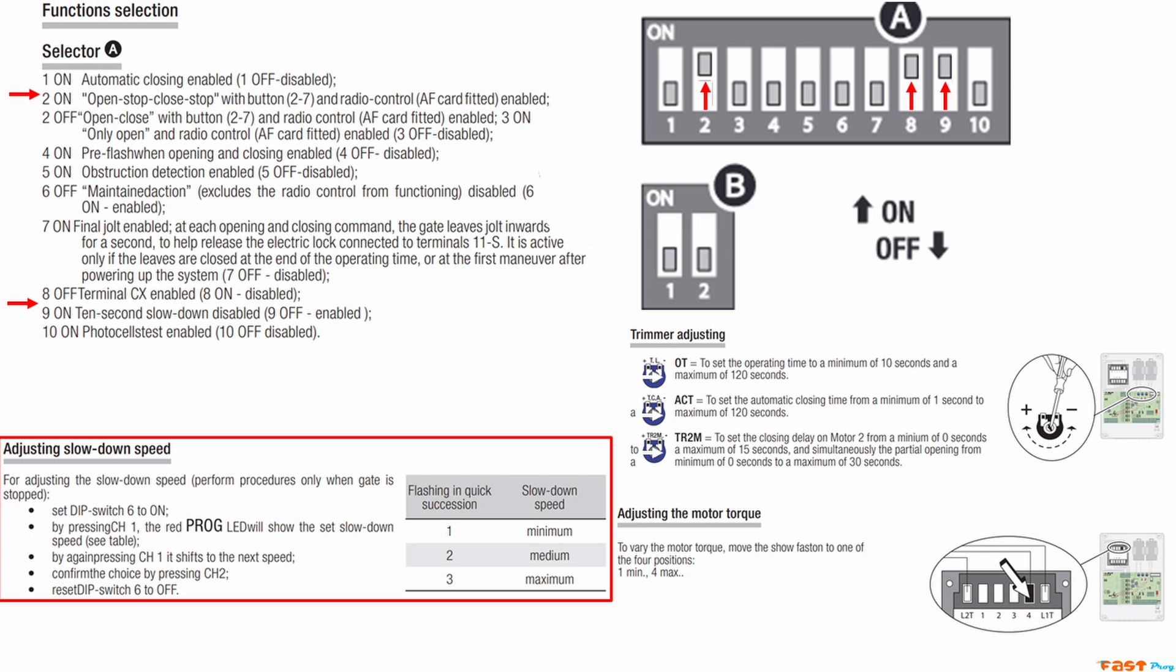You can fine-tune this later by increasing or decreasing the time so that the motors stop 2 to 3 seconds after the gates reach their stop points.